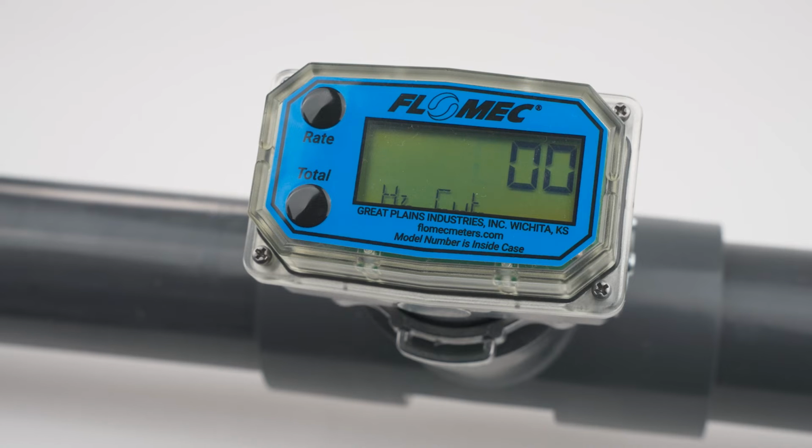Next, the meter will prompt you to select a low-frequency cutoff. This will enter a minimum allowed pulse input frequency to filter out any low-frequency input pulses which can be generated when the meter is subject to mechanical vibrations. These vibrations could cause the totalizer to add phantom volume to the displayed totalization values.